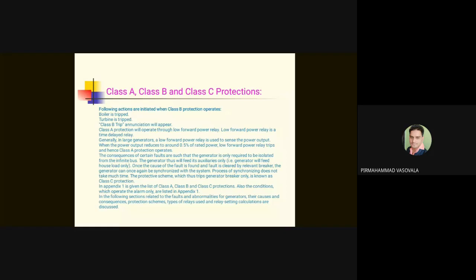If the line relays fail, actually, if you have studied the protective systems well, you might be knowing that for a transmission line, there is a distance protection. If distance fails, then there is a backup overcurrent and earth fault. If that fails, then the fault is rather thrown to the generator. Actually, in that case, there is a transformer secondary backup protection, right? If that fails, then only it will result in class C. That is, then the generator will see the fault, and the class C protection operates.